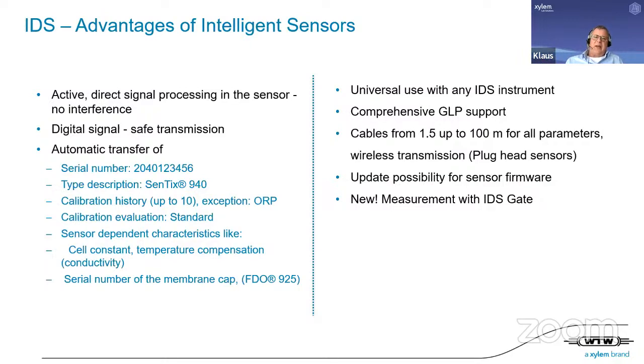We also have automatic transfer of all information, which can be used in a GLP environment, for instance. You need to know the serial number and the name of the sensor. The calibration history is also interesting to see how the sensor's condition or status changes from calibration to calibration.